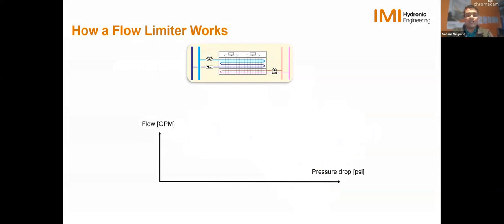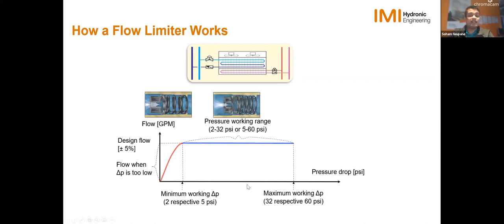And when we look at this in a chart, this is how it looks. We've got flow versus your pressure drop. When your delta P, or differential pressure, is too low, your valve really won't be doing anything. And as you reach the pressure range where the valve is supposed to operate, 2 to 32 PSI or 5 to 60 PSI are the most common pressure ranges we see. Depending on what pressure range you're using, within that range it is going to maintain that constant flow regardless of changes in the system, and you have no interactivity. And anything above that, you're just going to overflow, right? Your spring is not going to be able to take care of it.